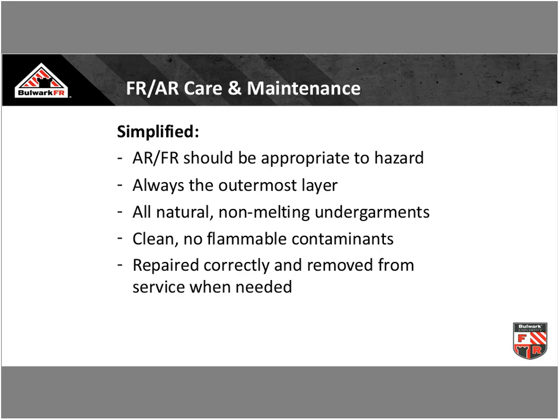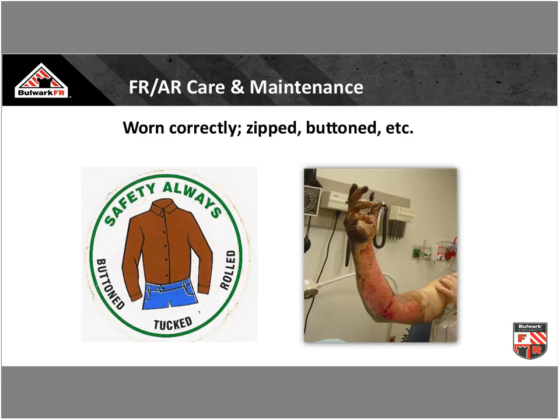Simplifying care and maintenance. Flame-resistant arc-rated clothing, always appropriate to the hazard. Always the outermost layer. Remember that picture we showed you with the hoodie on the back. At the very minimum, always natural, non-melting undergarments. Clean, no flammable contaminants even throughout the workday, and definitely make sure they're clean when you're taking them out of the wash and implementing them into the field at the start of the day. Repair correctly and remove from service when needed. Always, always wear it correctly, zipped up and buttoned.